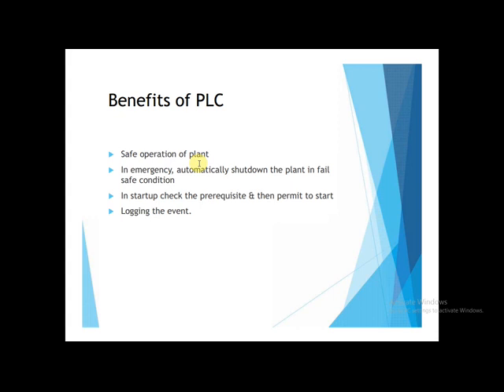The third benefit is startup pre-checks. Sometimes we cannot just start the machine — we need to check certain parameters. For example, for an engine we need to check whether there is certain pressure buildup, certain RPM achieved, and certain pre-checks have to be completed. This can be done in a PLC, which gives the start permissive signal only when certain conditions are met.